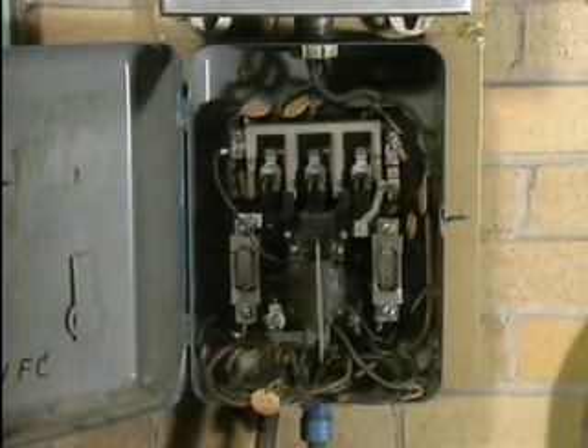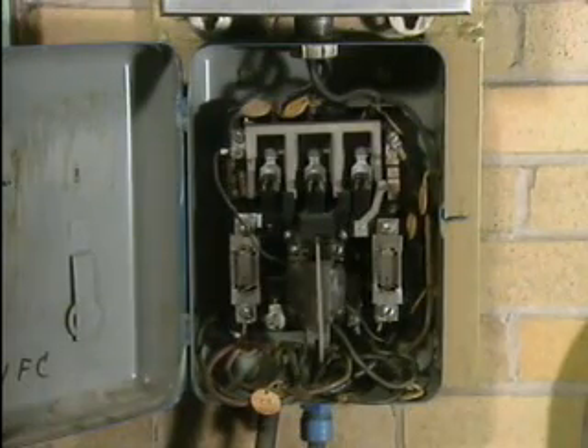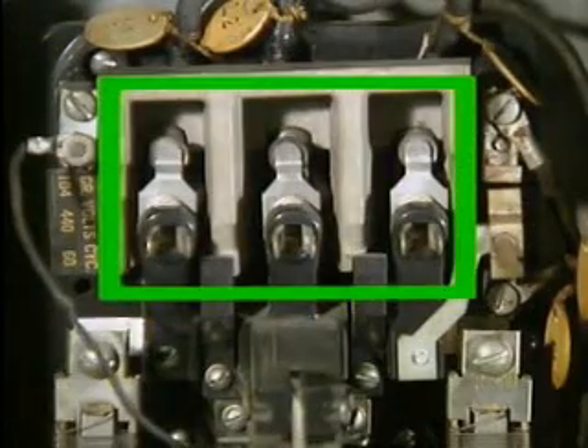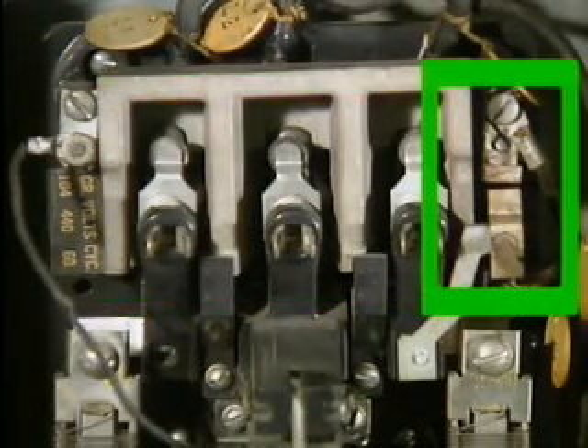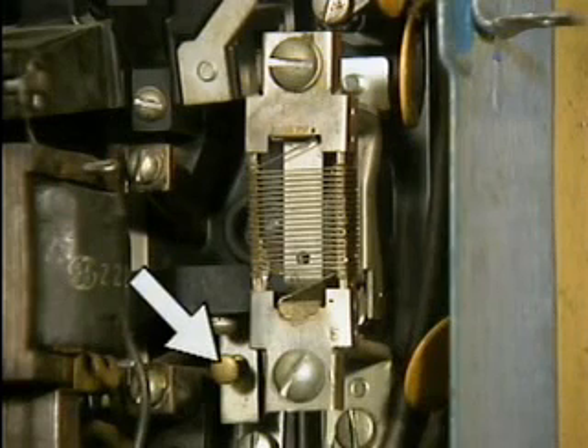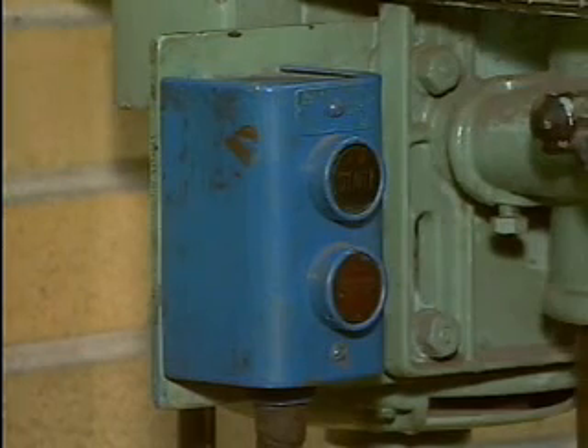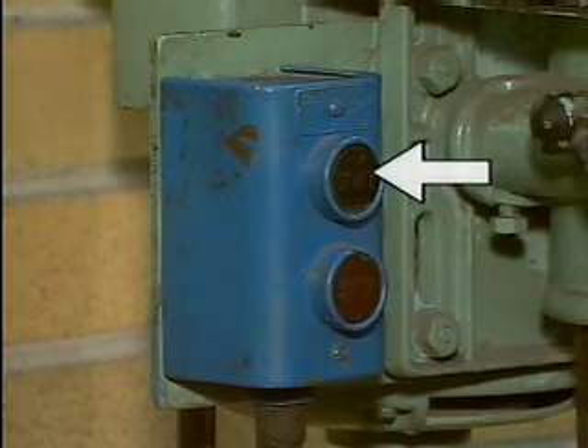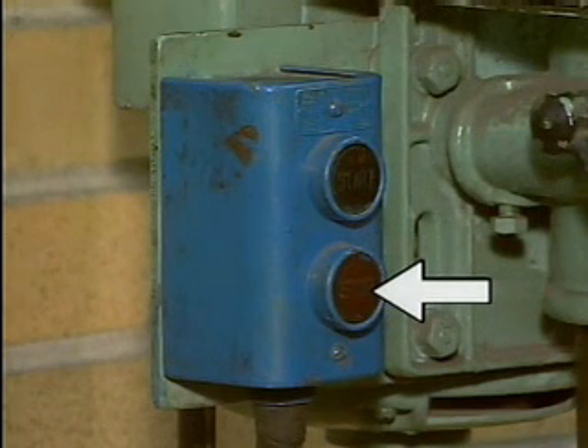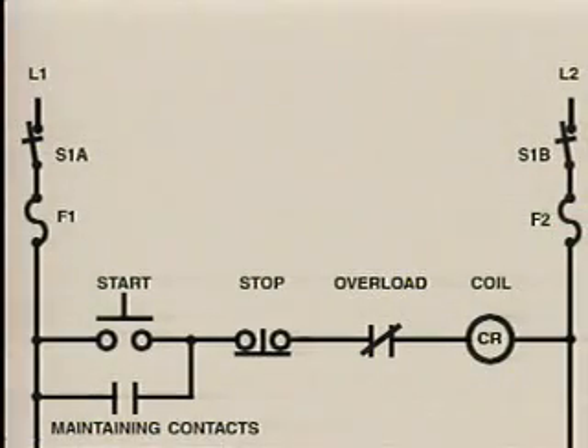The drill press's control cabinet contains a control relay and a set of normally closed temperature overload contacts. The control relay consists of a coil, 3 sets of power contacts, and a set of maintaining contacts. The temperature overload contacts are opened when the drill press's motor is in danger of being damaged by a thermal overload. The push-button station contains a push-button start switch and a push-button stop switch. We can use this illustration of the drill press's control circuit to see how the drill press operates.